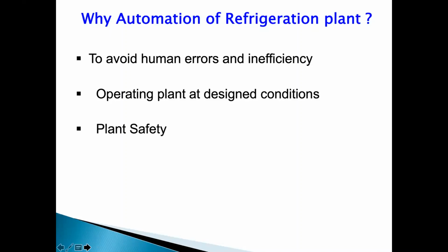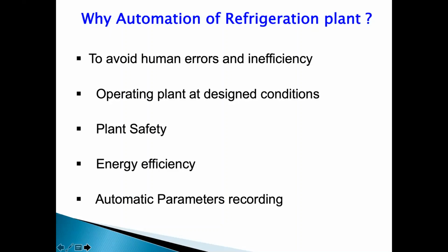Many times plants need to operate, like a multi-facility cold storage storing products from -20 to +5 degrees centigrade. You may have different operating conditions. You need to control all of this and make it automatic, less dependent on humans, and use human beings for other more efficient purposes. And of course, as I said, ammonia is toxic. We have to implement safety measures to make the plant safe for human beings to operate. And of course, energy efficiency, as we are talking about, is one of the most important parts.